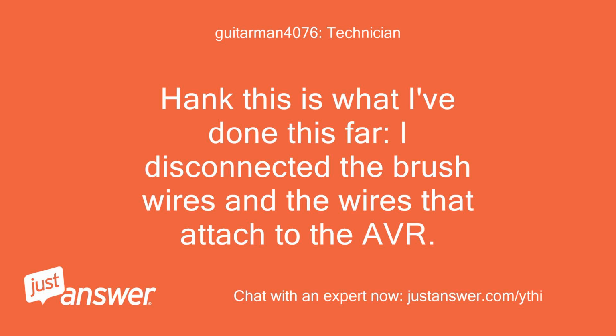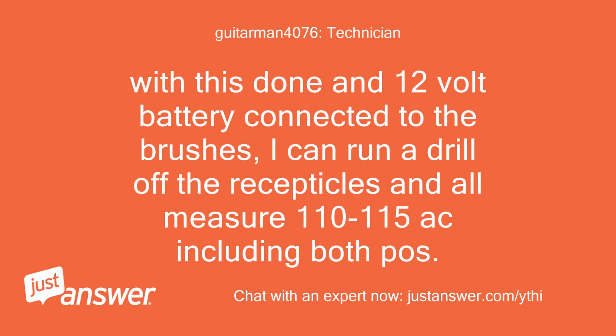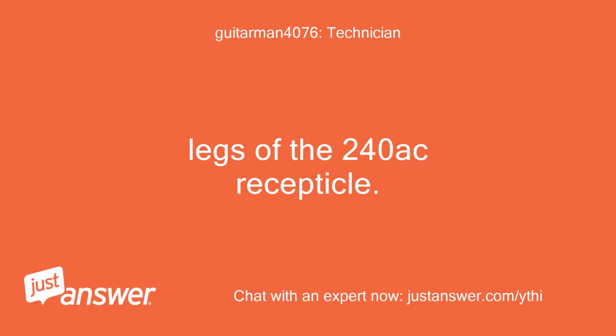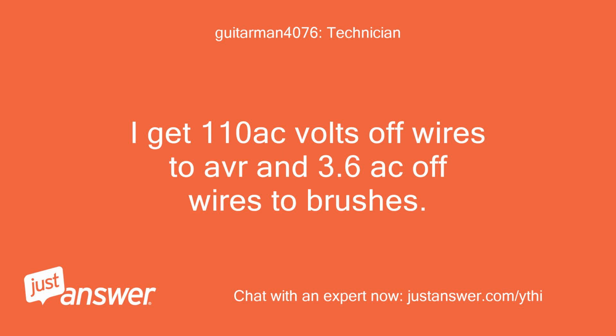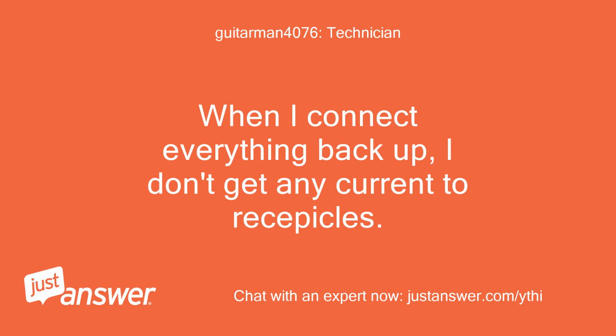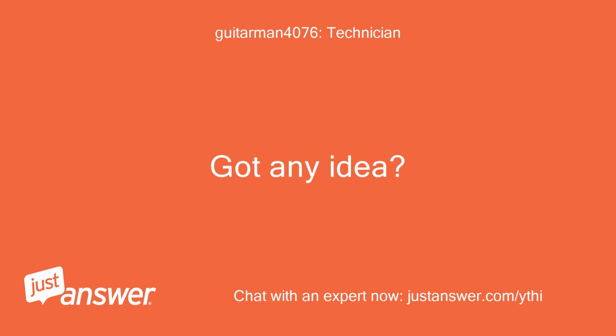Hank, this is what I've done so far. I disconnected the brush wires and the wires that attach to the AVR. With this done and a 12-volt battery connected to the brushes, I can run a drill off the receptacles, and all measure 110 to 115 AC, including both legs of the 240 AC receptacle. I get 110 AC volts off the wires to the AVR and 3.6 AC off the wires to the brushes. When I connect everything back up, I don't get any current to the receptacles. Got any idea?